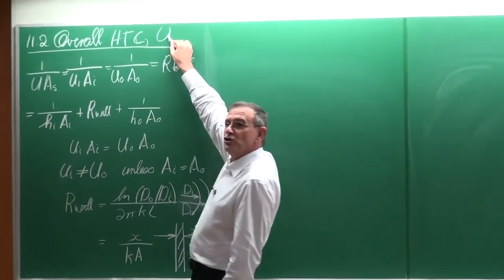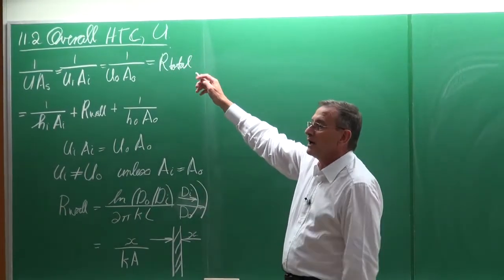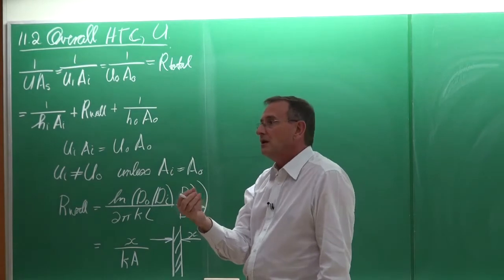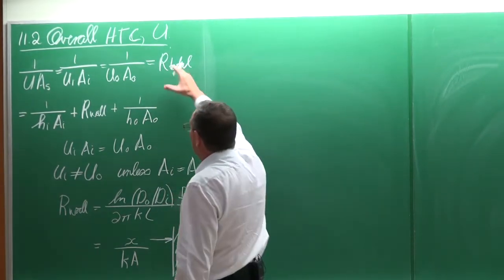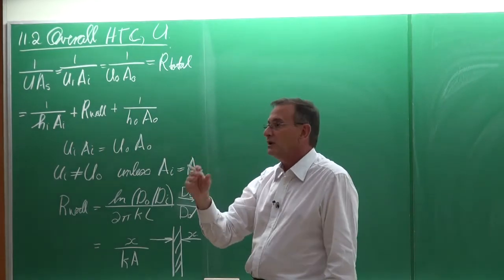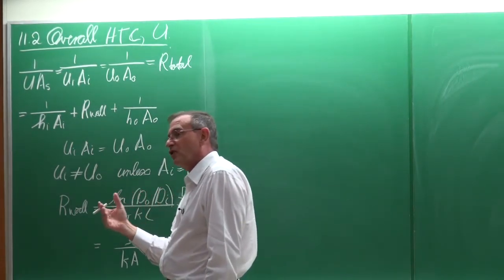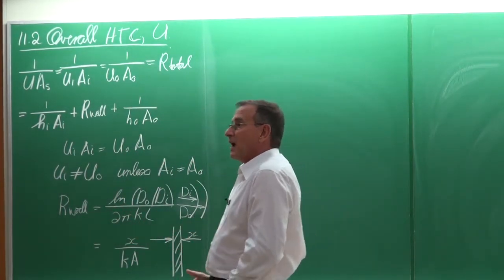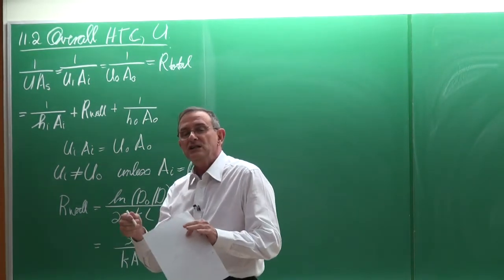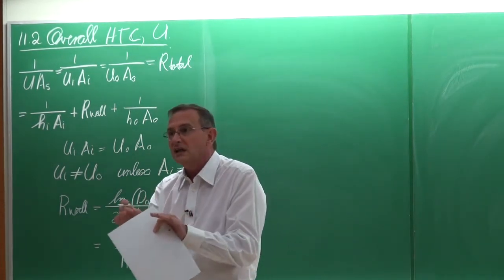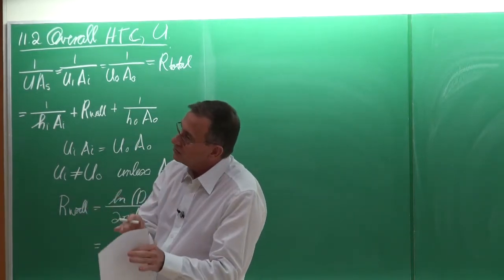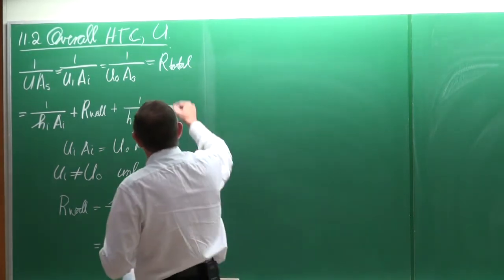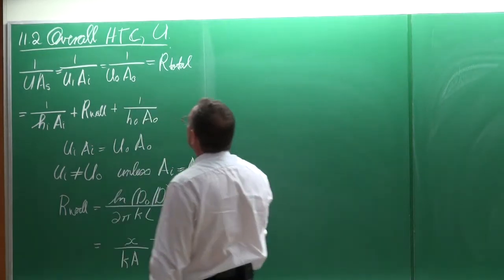What is the idea of getting U? The idea is to make things simpler — to have a heat exchanger and tell an engineer the overall heat transfer coefficient value. If you have that value, you can calculate the heat transfer rate, or if you have the heat transfer rate, you can calculate the delta T, without needing to go into all the detail of the heat transfer coefficient on the inside stream and on the outside stream.